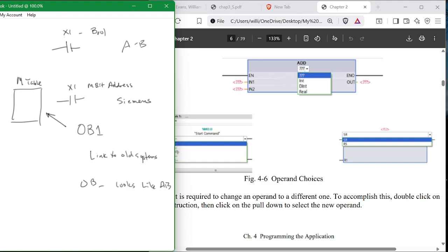Another thing that might happen is you say, I'm looking at this coil, this rung of logic, and it's green all the way across, but the bit that is the output bit is off. You know what the first thing I'm going to tell you is? You double used that bit. And about 90% of the time I'm right. I've been through this war enough. One of the first things you're going to do is forget and double use a bit. It's natural. It's the thing that not everybody, but some of you will do.